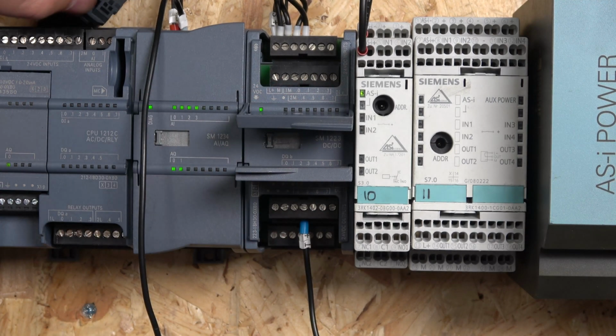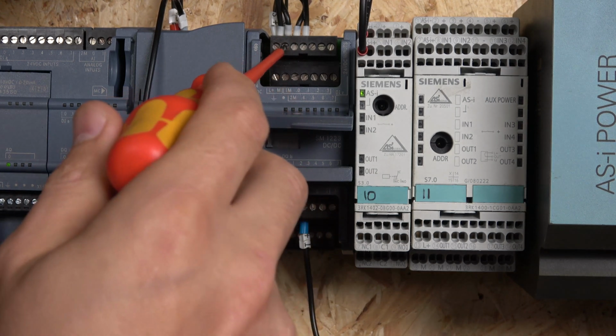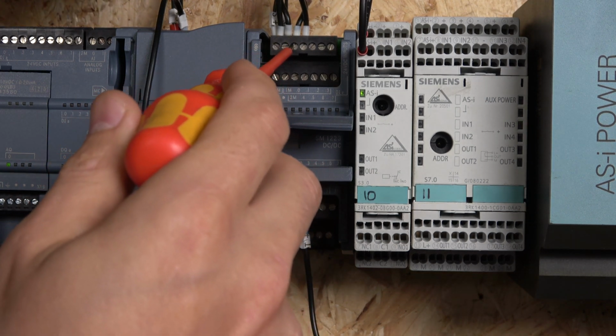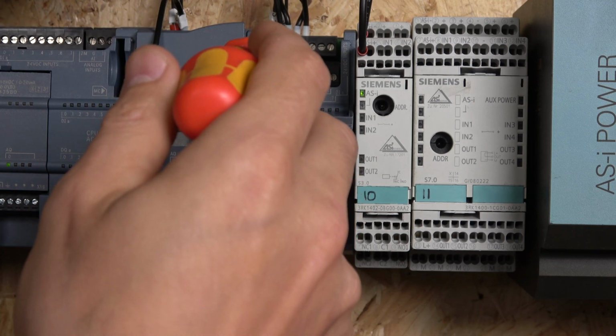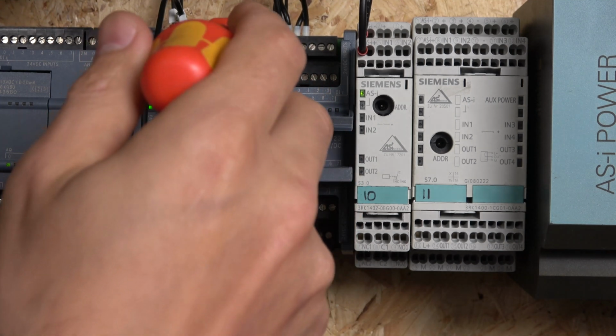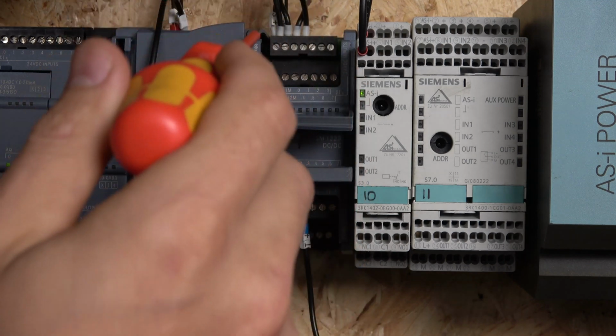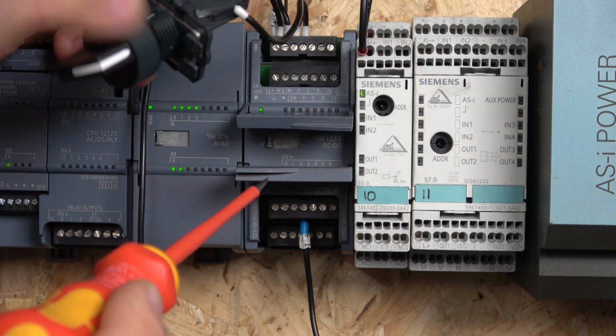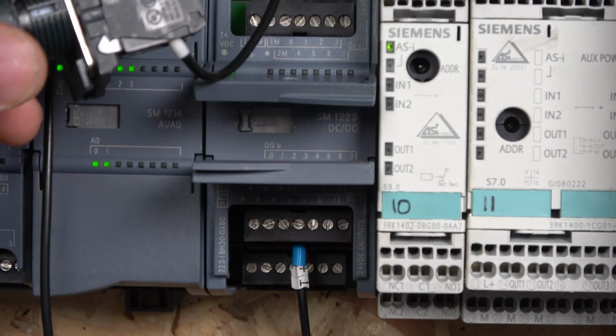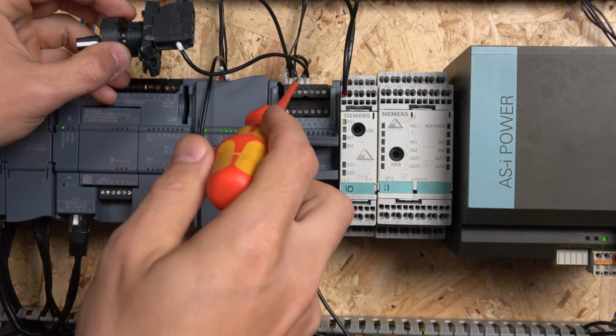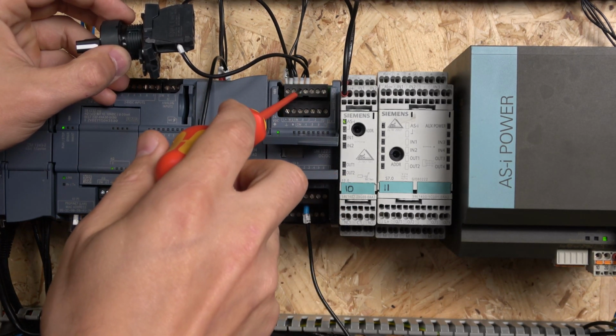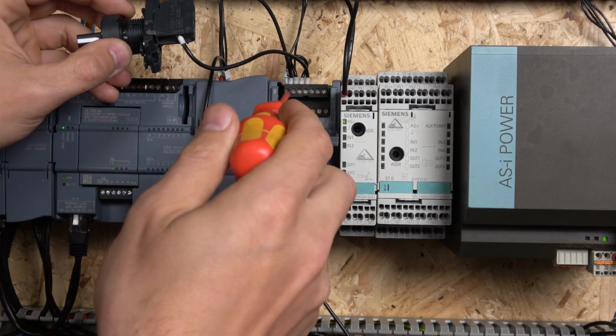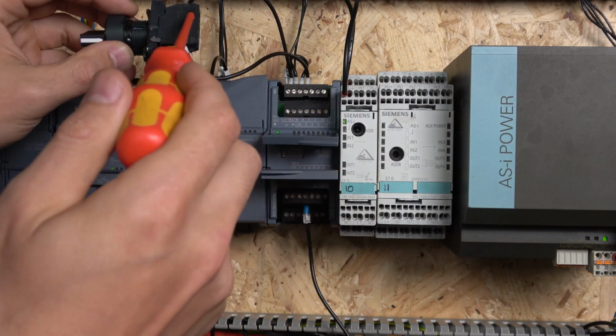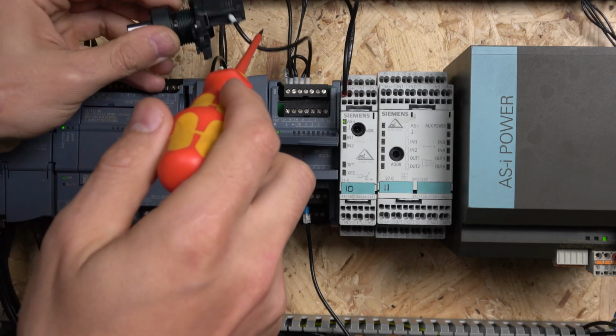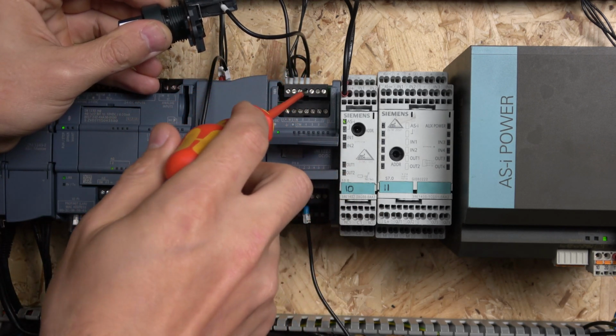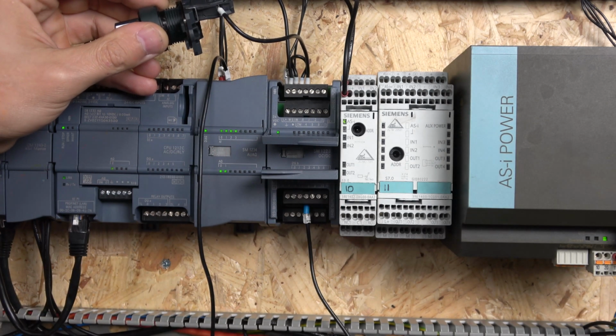In my case, as you can see down there, I have linked it out. I have taken the M from here, shipped it across, and the negative in here goes to my 1M, and then I take a plus from here, because again, it's the same power supply. Let me just zoom out a little bit. As you can see, I am sending M to the 1M in here, and I'm taking 24 out of this guy, sending it to my switch, and that switch will send the power back into my input, and that input will come on. We're going to check that in a minute.